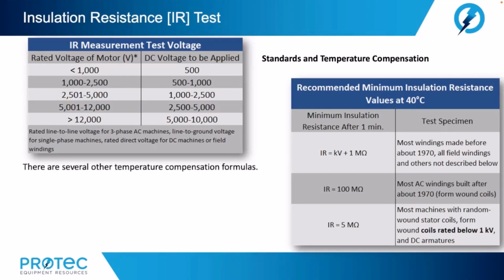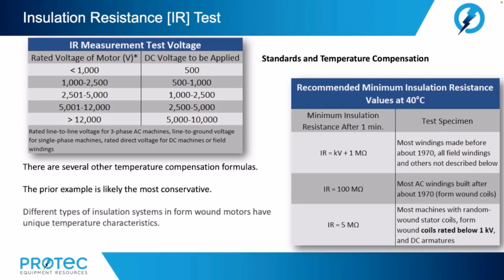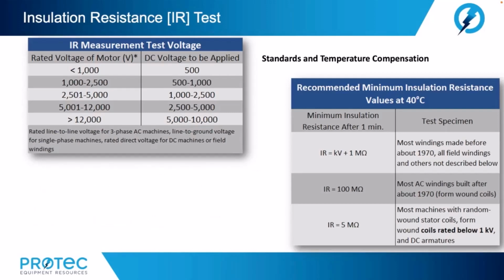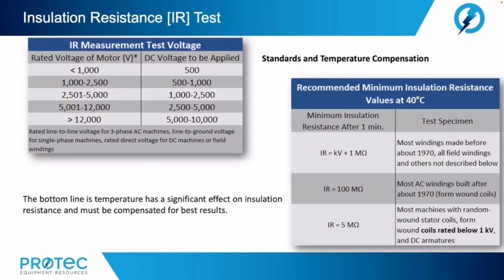Now, there are several other temperature compensation formulas. The prior example is likely the most conservative. Different types of insulation systems in form wound motors have unique temperature characteristics. Now, these are only obtained from the manufacturer of the motor. The bottom line is temperature has a significant effect on insulation resistance, and it must be compensated in order to get the best test results.